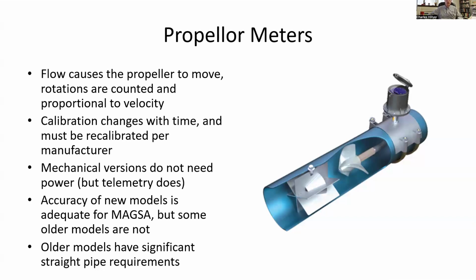So these newer models have lower what's called straight pipe requirements, but the older models and some of the models that are still on the market require a significant amount of straight pipe upstream and downstream of the meter. If you don't have that straight pipe upstream and downstream, you're going to be getting erroneous measurements from those meters. Some of the newer ones, like the one in this picture, have a flow straightener, which reduces that straight pipe requirement, but it doesn't make the requirement go away. So you have to take that into consideration when you're choosing this type of meter to make sure you actually have room to install all that straight pipe.